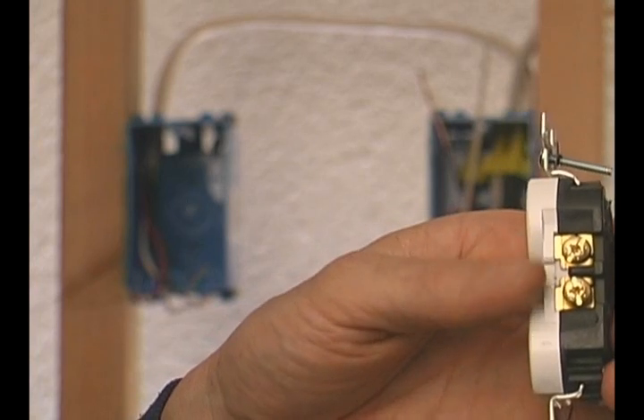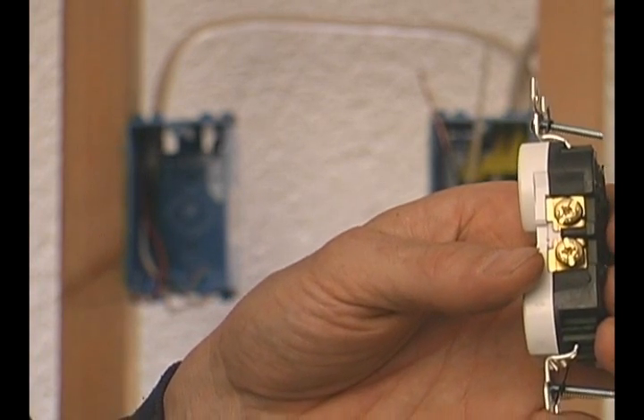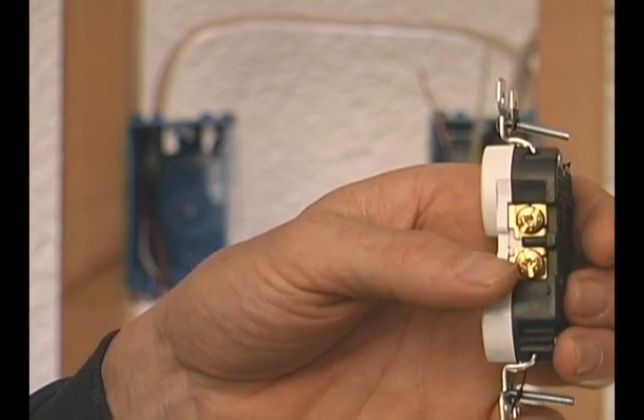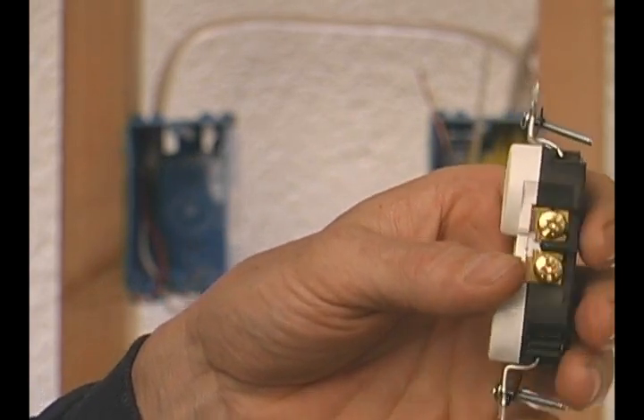so these two screws are not connected anymore. A wire that lands on the top part will not energize the bottom half. Now, we do nothing to the neutral side. There's also a tab...